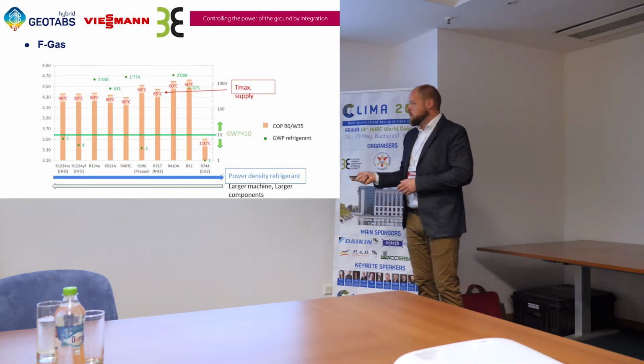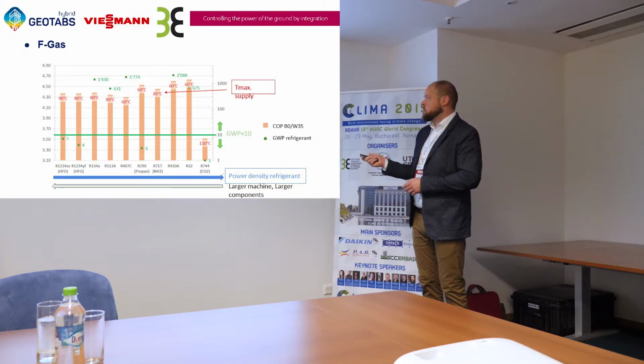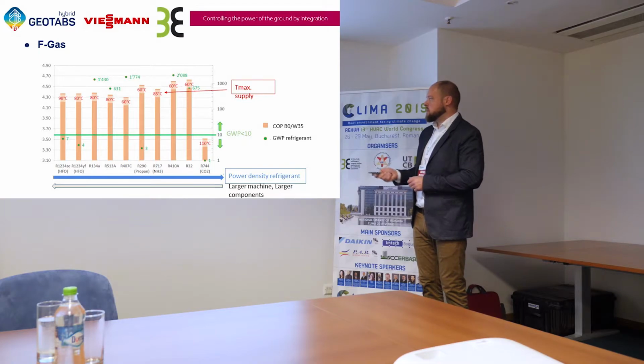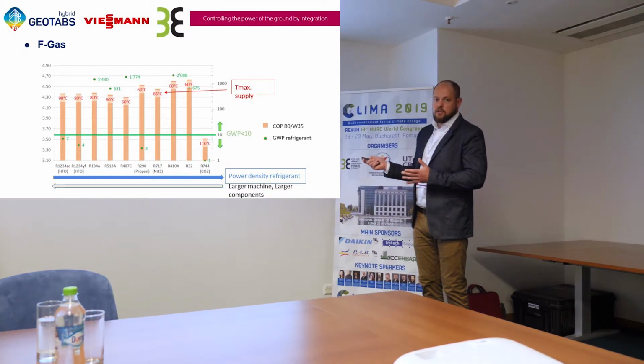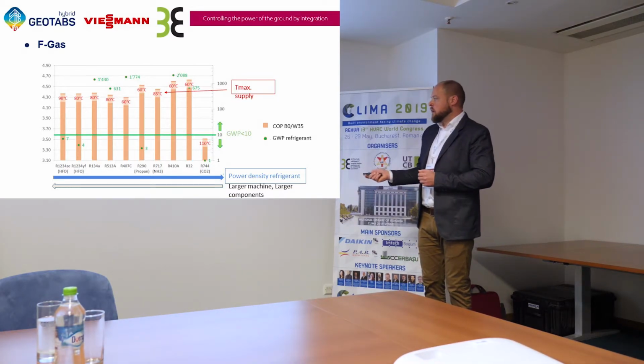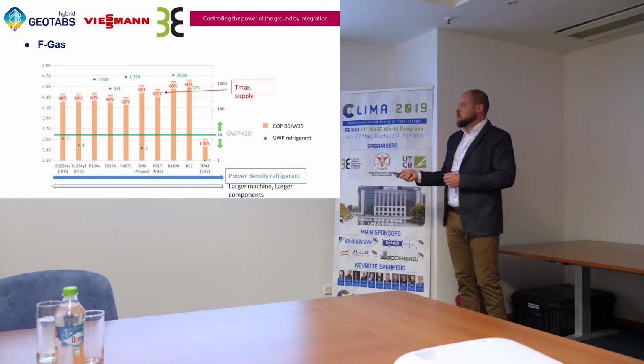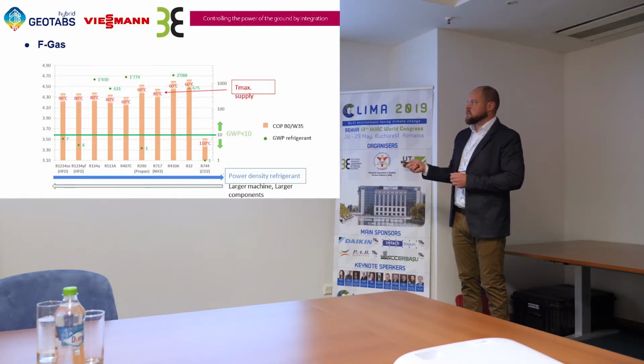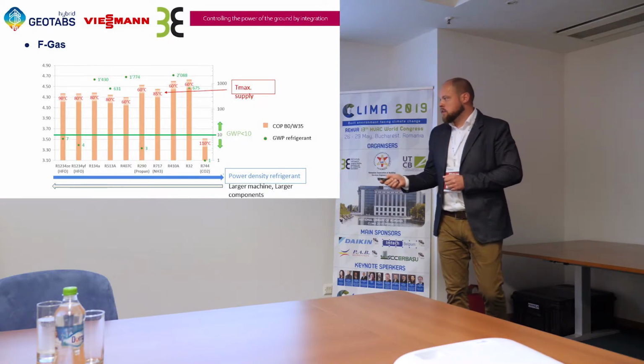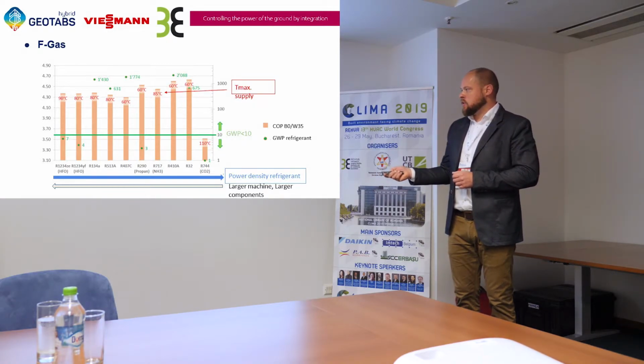So you see here the 410A has a GWP of 2088. The maximum departing temperature we can make with this heat pump is about 60 degrees. And you see the COP of this system is about 4.6, as we showed in the table. Other refrigerants used today, R32 also has a departing temperature of 60 degrees on the secondary side, and the COP is comparable to the R410A. When we look at other newer refrigerants, the HFOs here, you see that the COP is a bit lower, but the departing temperatures on the secondary side can be much higher.